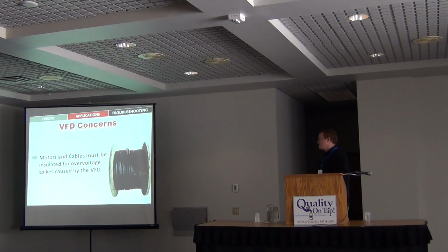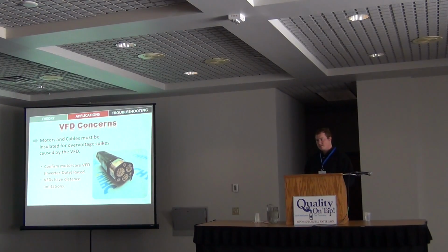Another thing of concern is VFDs supplying motors. The motors and cable have to be insulated for overvoltage spikes caused by the VFD. Because of the electronic switching within the drive, on a 480 volt VFD, it's converted to the DC bus, which is 600 volts. I think 690, I believe, is pretty standard for the DC voltage in those drives. And then it's output to the motor, and because of this switching, it's not just a 90-degree switch. There's a little overshoot and undershoot voltage that you could have, combined with the distance to the motor. It's called capacitive coupling. Voltage at your motor can be almost 1400 volts, which is why you see a lot of times an inverter duty rated motor rated at 1600 volts.